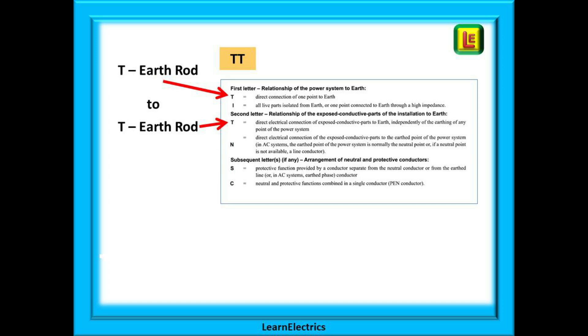And finally for us a TT system. T for earth. And again T for earth. This indicates that the earth electrode at the installation is electrically independent of the earth electrode at the supply transformer. There is no copper conductor connecting the two earths together. We must rely on a connection through the soil or ground. This is not as good an earth connection as the previous two systems which is why TT systems must be given extra consideration for safety.